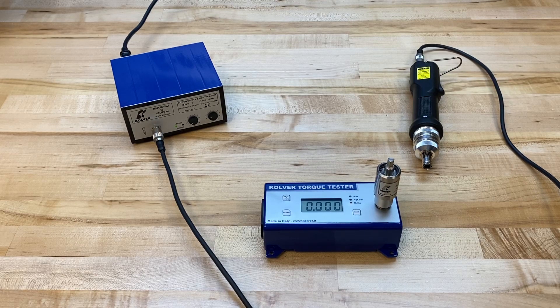Today I want to provide a brief tutorial of presetting and validating torque using our FAB and RAF series of clutch-controlled electric screwdrivers by Kolver.